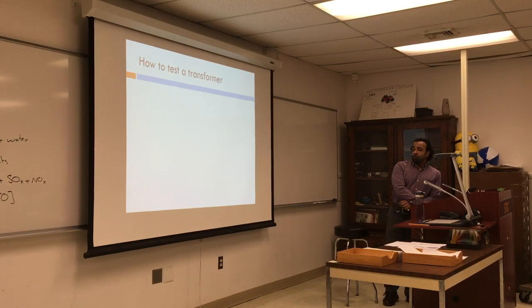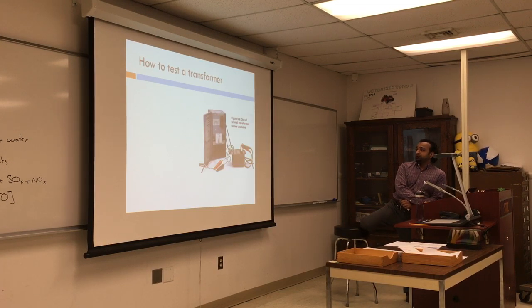How to test a transformer? We're going to go over the steps again. Before you condemn a transformer, you want to make sure that it's not good, because again, a transformer is not cheap. It's around $150 to $200. And if you change a transformer and it's not the issue, you're still going to have delayed ignition.